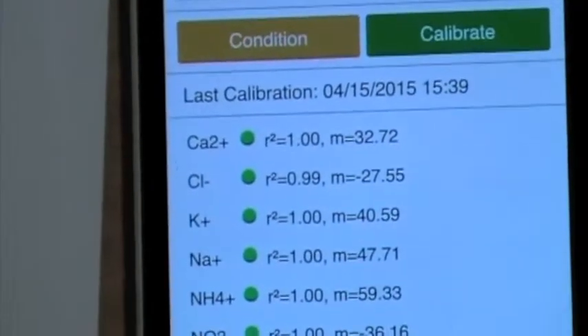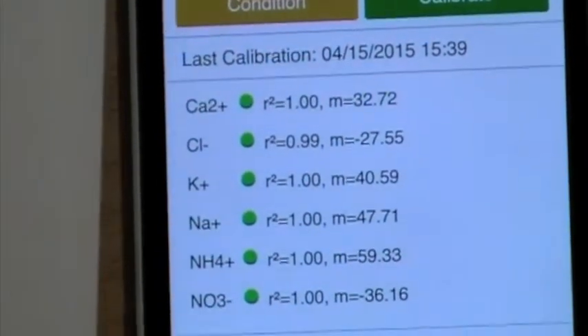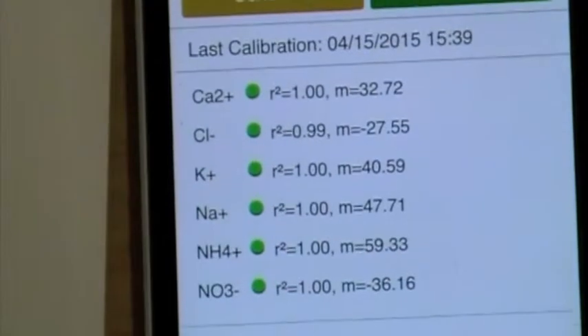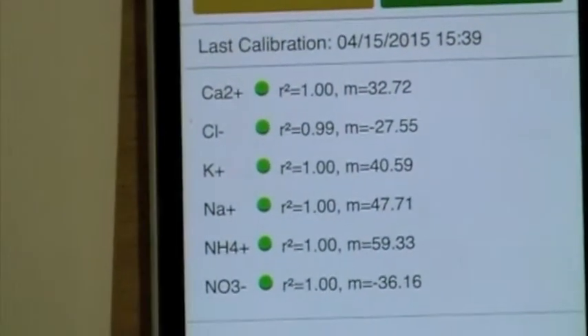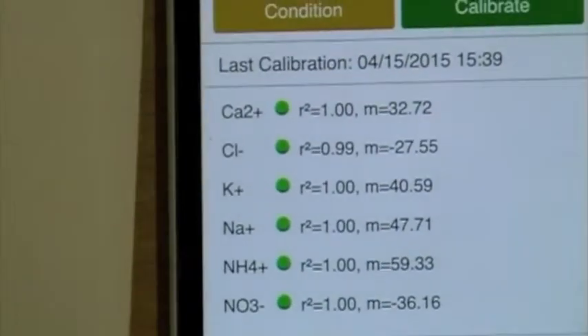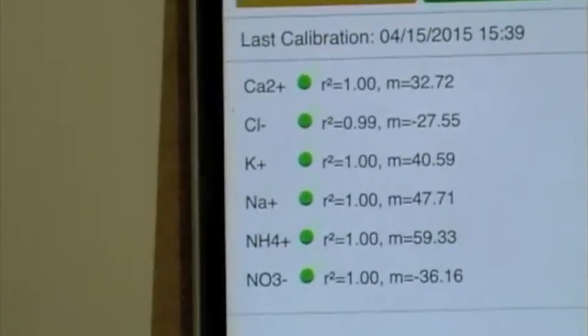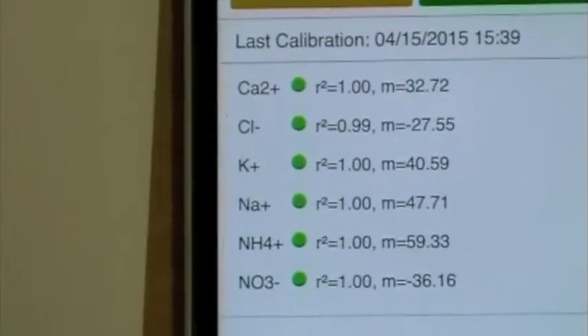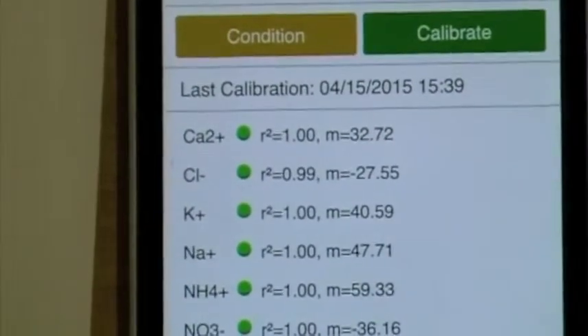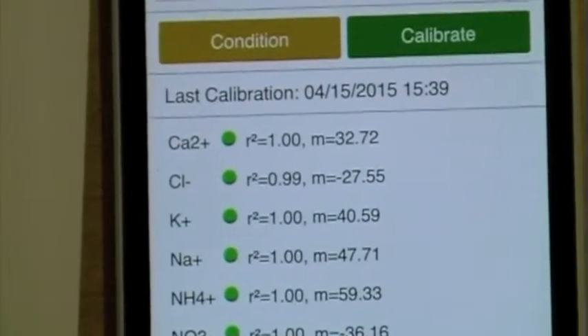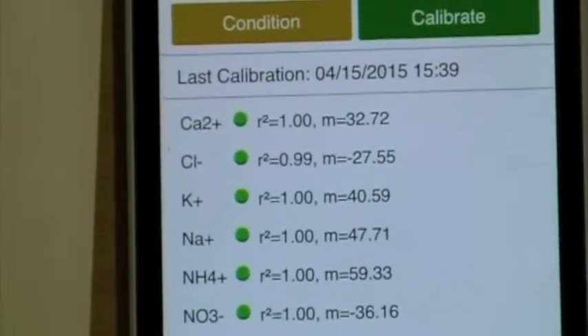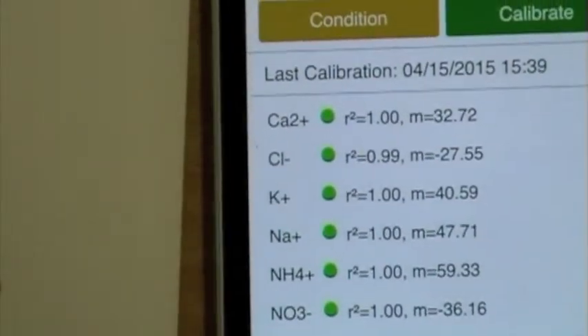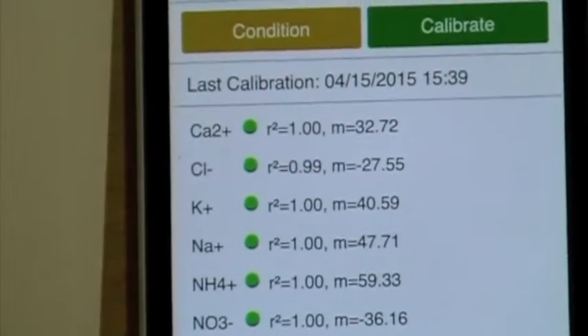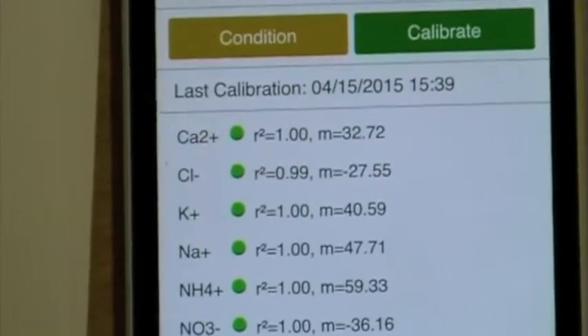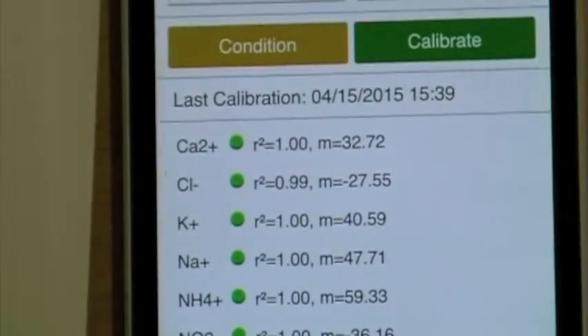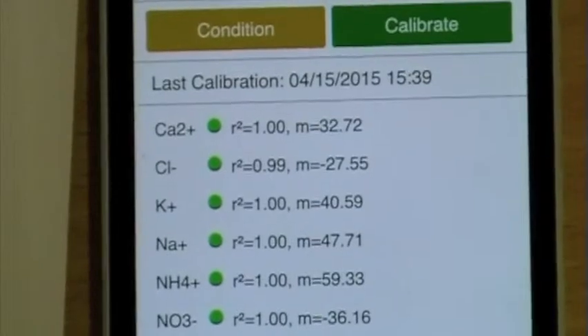What the screen means is if you're drawing a graph and you got a straight line, then the R square is 1. The closer to 1 the better. If it's not 1 or close to 1, it will turn orange or red. Red is bad, orange is okay, green is the best. The values next to M stands for the slope of the curve. Should be negative for the negative ions, chloride and nitrate, positive for everything else. The lower the number gets, the older the probe, but don't worry too much about these for now.